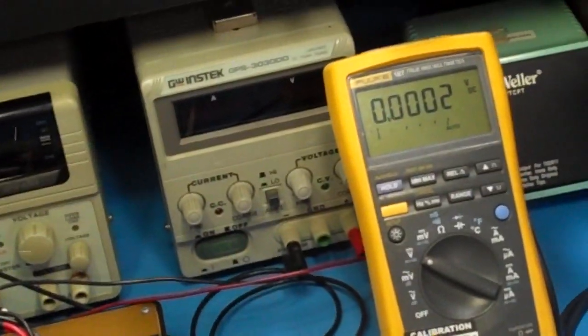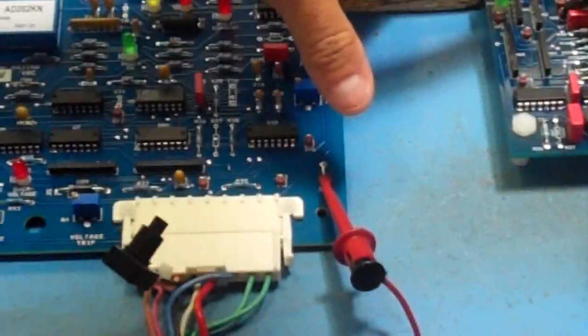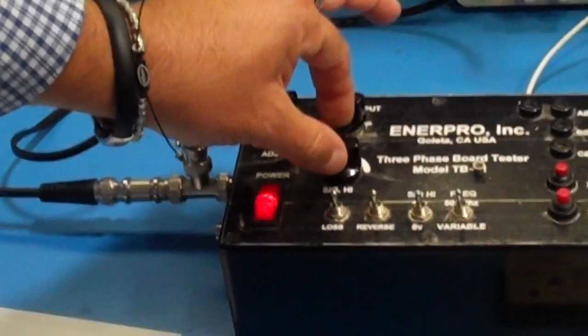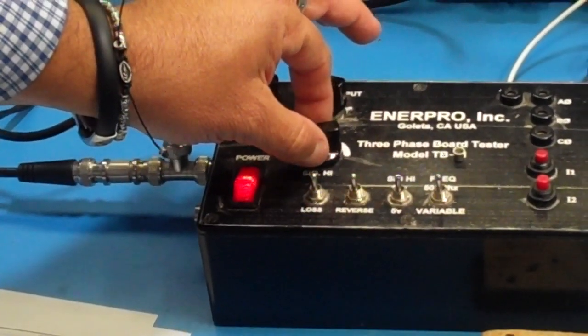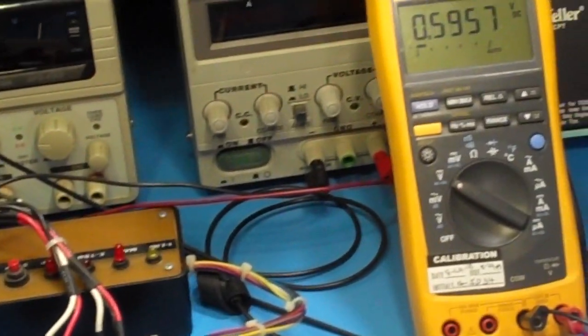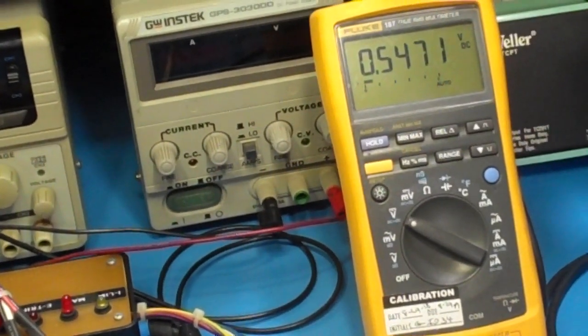It's at 0. The 2100 board has a low signal inhibit. That's why we have that red LED, which will not clear until I increase sig high here with my potentiometer to about 0.4 of a volt.